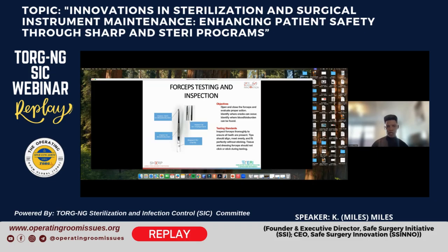You also want to make sure you go down the handle area where the grooves are to make sure there's no bioburden there. A lot of times in that part, you'll get a lot of rust, because that's normally where the surgeon is going to be holding it, so it's going to have more contact with blood and tissue from the patient. You also want to go down to the bottom end and make sure that you're inspecting that area for cracks. You'll see a lot of rust and pitting start to form in this area over time.